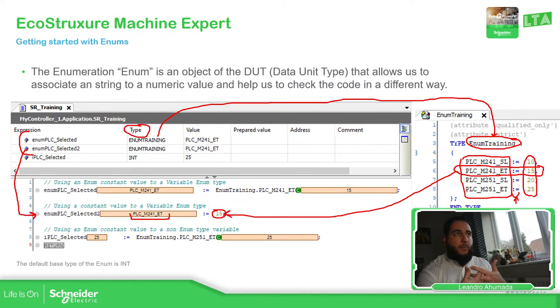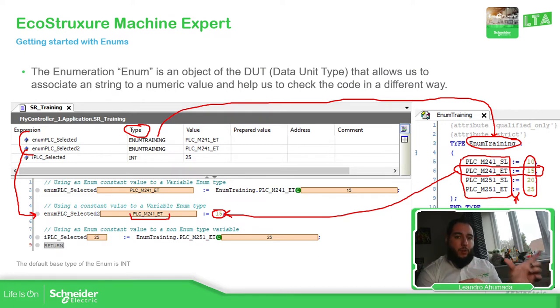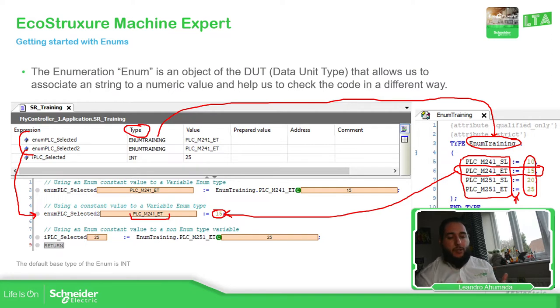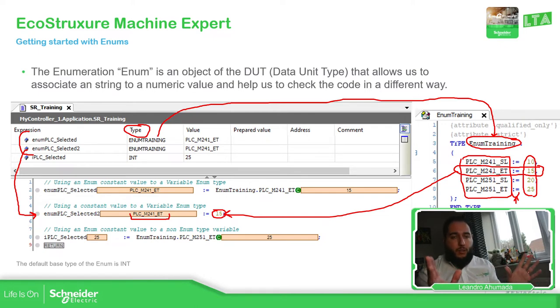So this is one way to understand the enums. I assign a constant value — the number 15 — to a value type enum. When I automatically assign the constant value to the variable with the enum, we should be able to see the text. So instead of trying to remember which is value 1, 2, 3, 4, we can link to the variable a text to easily identify what it is. When I assign the value 15, I can identify that the PLC selected is the M241 with Ethernet, just to have an idea.